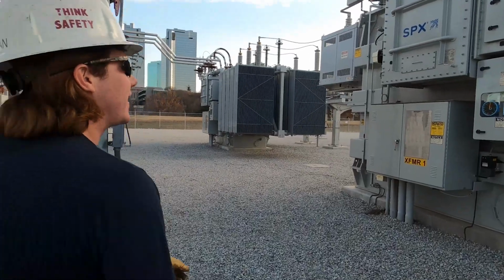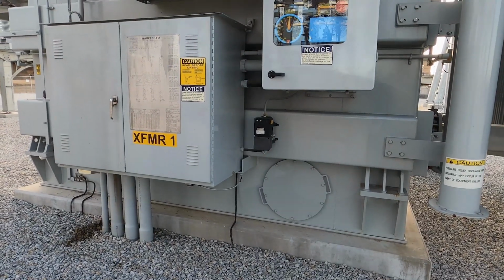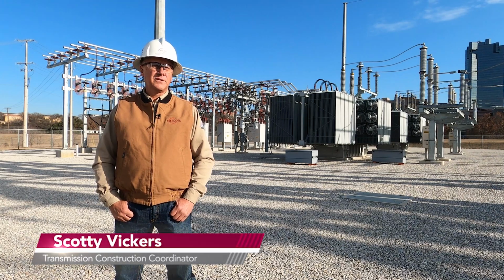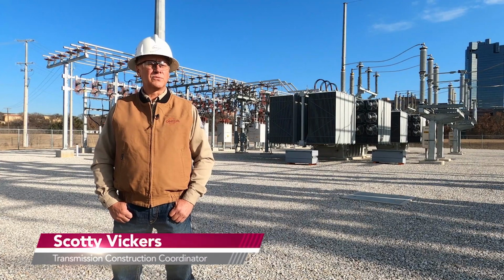This is a 138 distribution transformer. I go through all the equipment, make sure everything is operating as it should. All the switches that are supposed to be closed are closed, and all the switches that are supposed to be open are open. And it's checking heaters in the cabinets, checking oil levels on transformers.